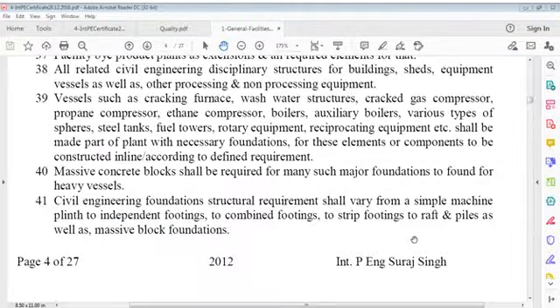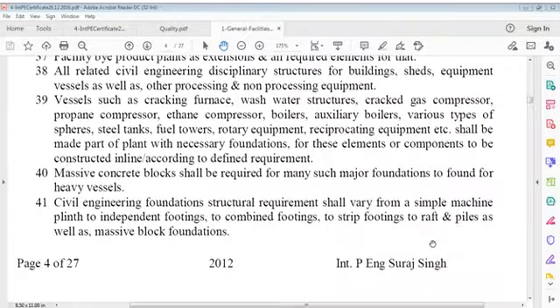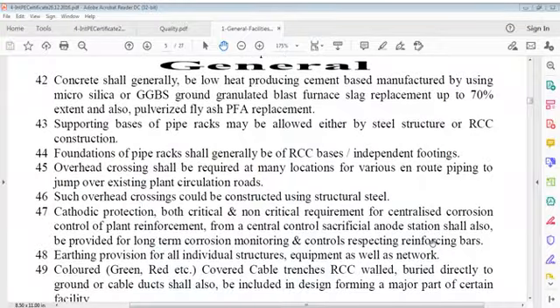Civil engineering foundation structural requirements shall vary from a simple machine plinth to independent footings to combined footings to strip footings to raft and piles as well as massive block foundation. Concrete shall generally be low heat producing cement, manufactured by using microsilica or GGBS, ground granulated blast furnace slag, replacement up to 70% extent and also pulverized fly ash, PFA, replacement.